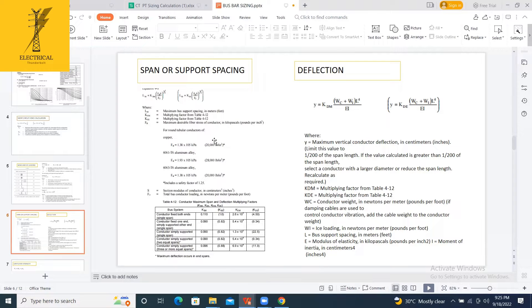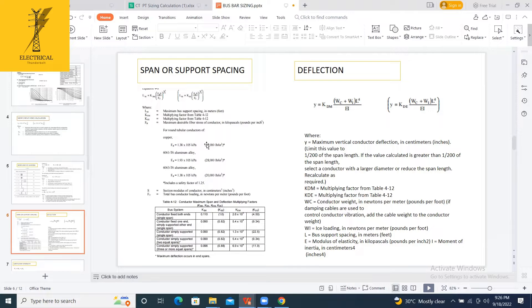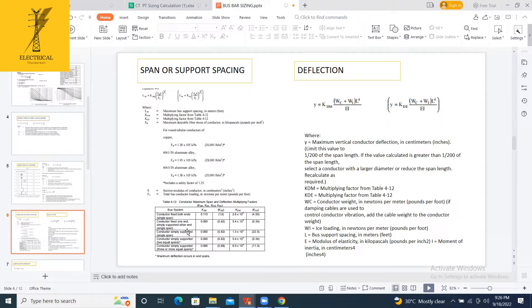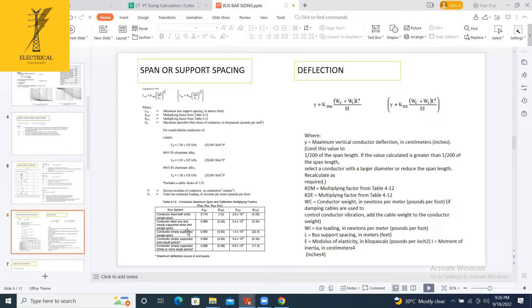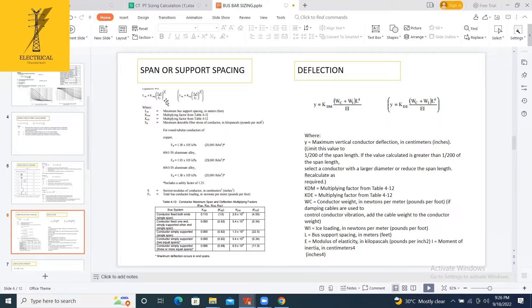It also depends upon multiplying factors like KSM, KSC, which depend upon the conductor, whether the conductor is fixed at both ends, fixed at one end and simply supported at one end. Based on that, the KSM, KSE, KDM and KDE are there. These are multiplying factors. Based on this, I am calculating the span now.